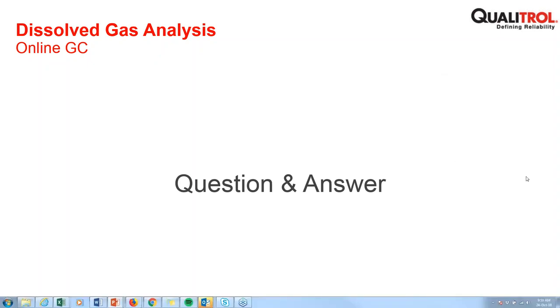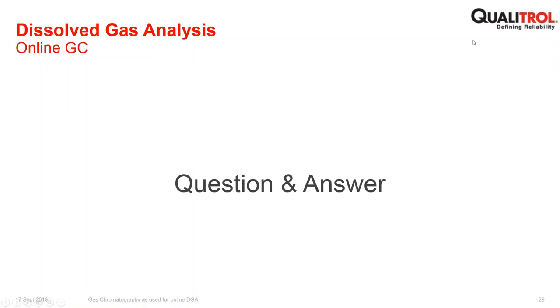We talked about some different diagnostic methods, Duval and whatnot. What is your recommendation for how people should use all of those and put them into their predictive maintenance program? So I would say that all of those diagnostic systems should be used with a level of caution. For example, in isolation, the Duval triangles and pentagons will always give a diagnostic regardless of the concentration. So you must give consideration to the quantity of gas.